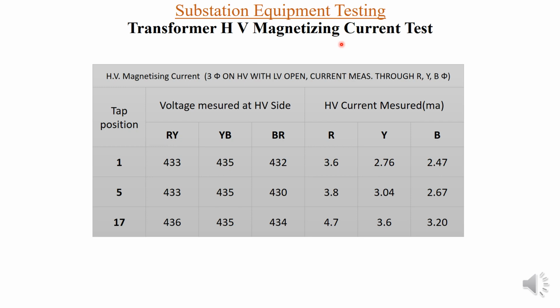Why does this current come in milliamperes? The reason is that this is a no load current, which is basically the core loss of the transformer, so it has to be in milliamperes. The lesser the value of this current, the better it is.